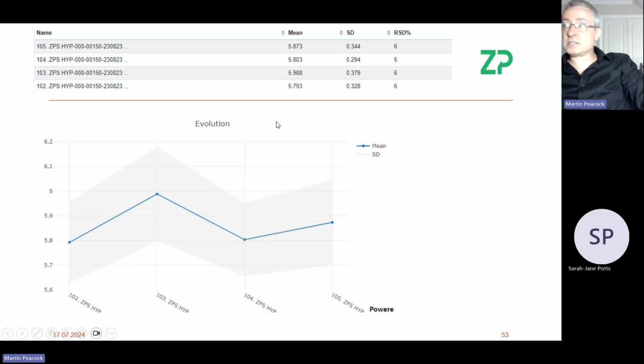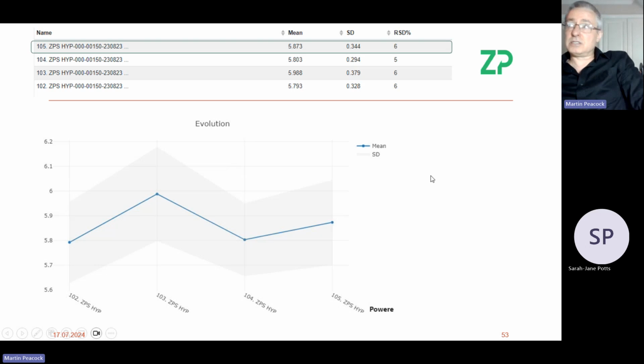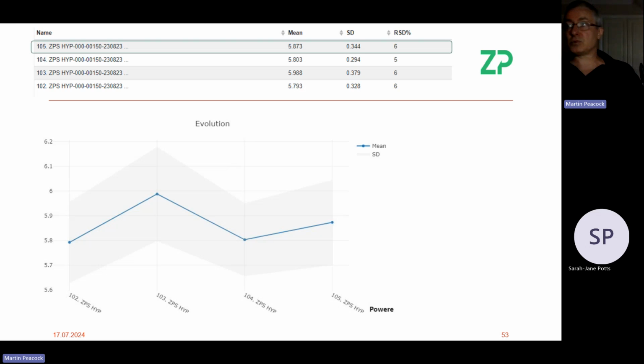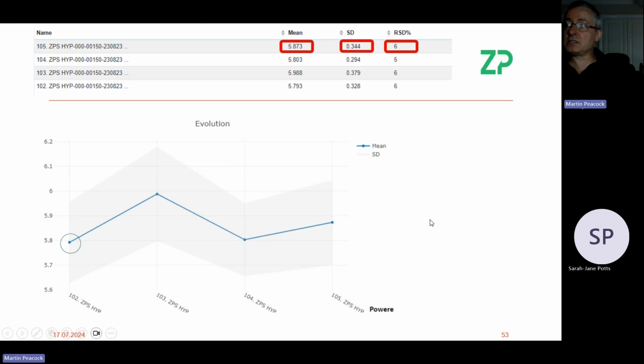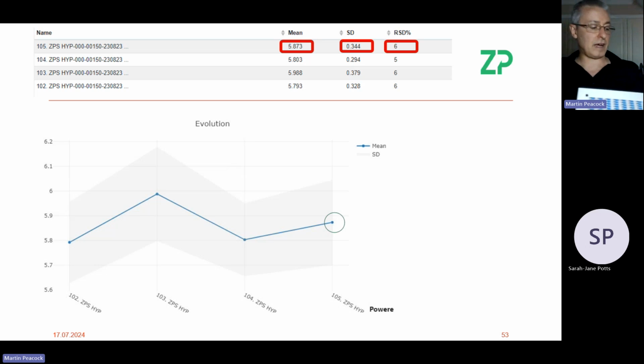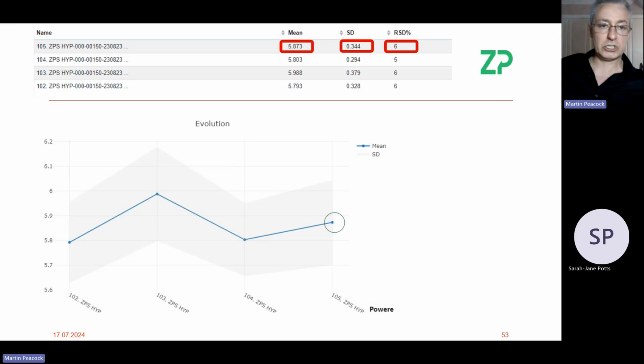So we will look at the peak heights, we will look at the standard deviation, and we'll try and make sure that our relative standard deviation is single digits. So we're looking at a production line where we may produce 21 to like 100 sheets, and then we'll test within that production batch to make sure that our repeatability or our relative standard deviation is 6%, in the next case 5%, in the next case 6%, in the next case 6%. So you can understand that the underlying repeatability is good enough that you can get a signal out that's proportional to concentration, and not proportional to concentration and some offset that's due to the irreproducibility of the underlying electrodes.